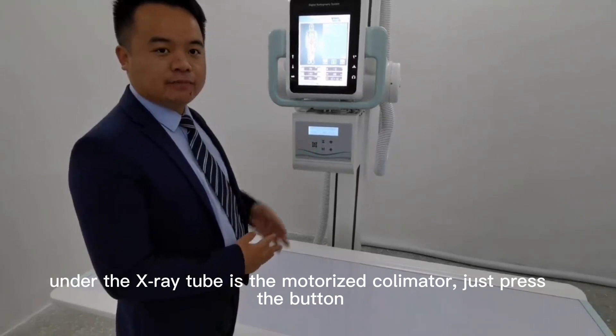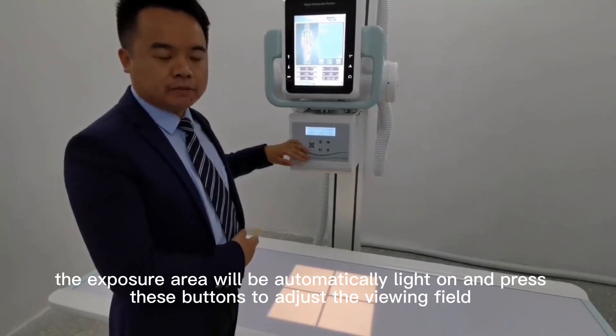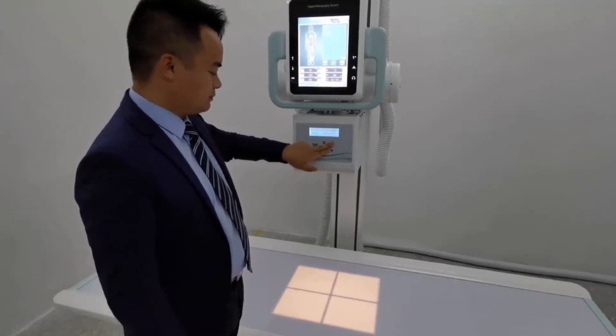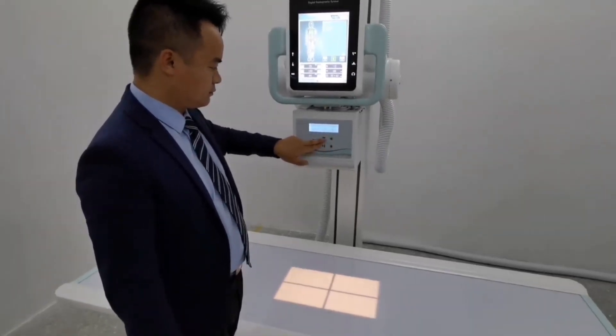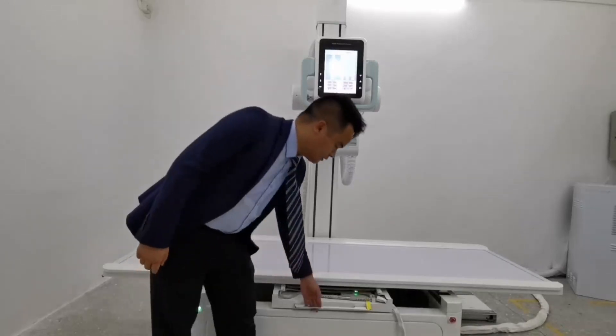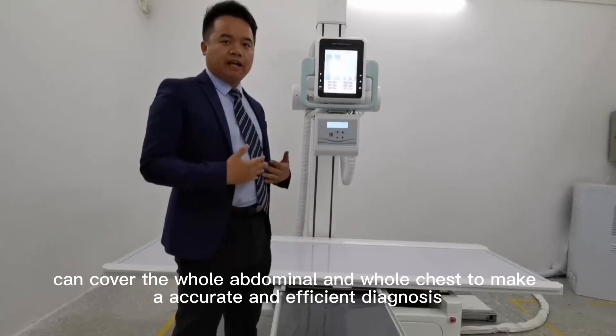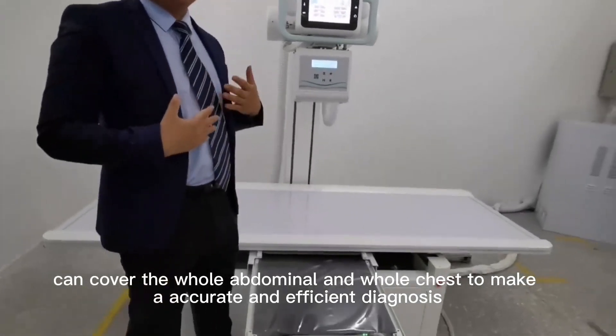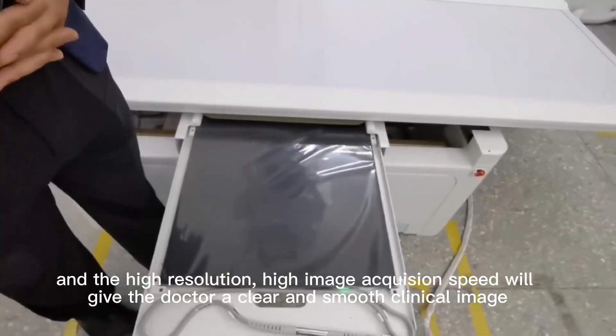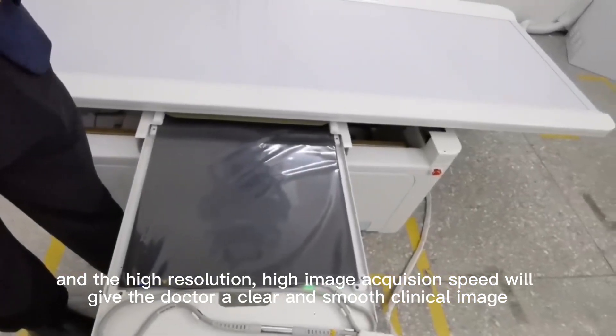Under the X-ray tube is the motorized collimator. Just press the button to control the exposure area. Under the table is our flat panel detector. The large flat panel detector can cover the whole abdomen and the whole chest, to enable an accurate and efficient diagnosis. The high resolution and high image acquisition speed will give the doctor a clear and smooth clinical image.